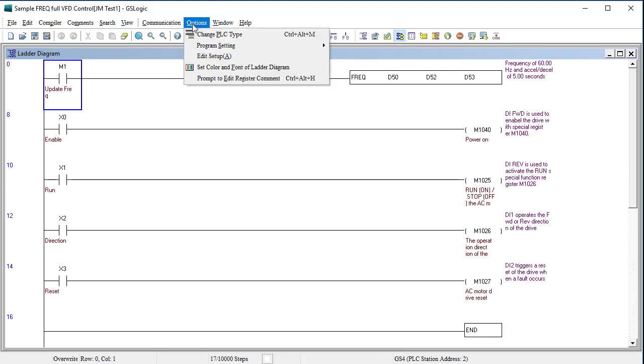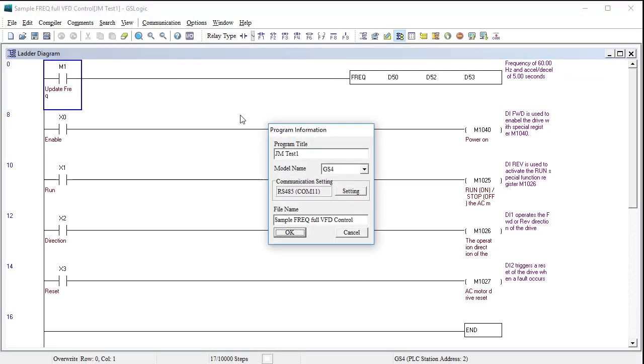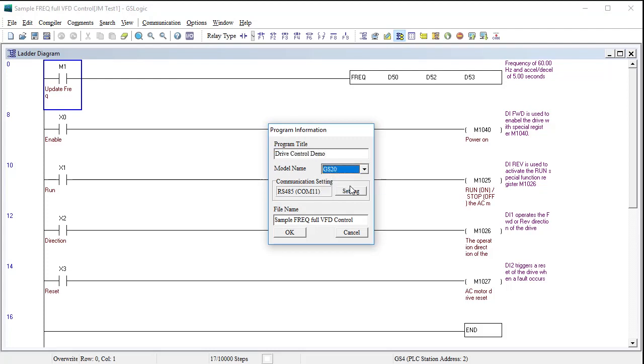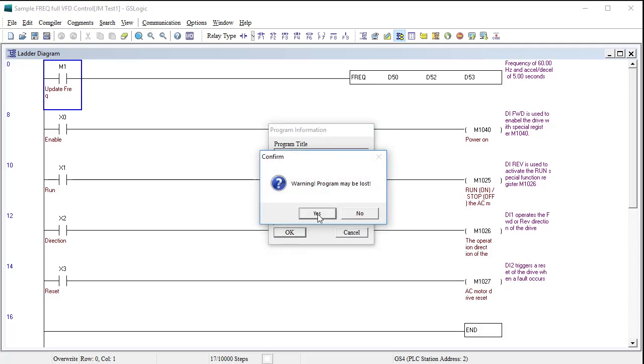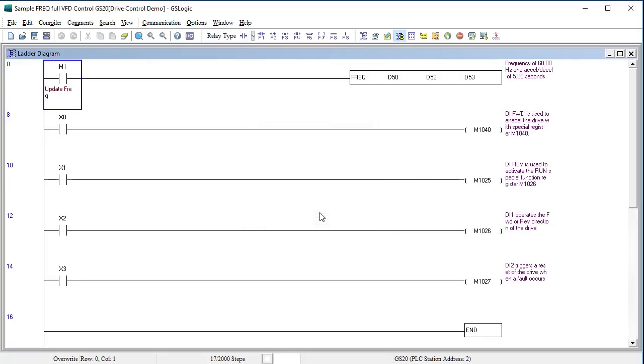The good news is, it's easy to change. We just go to options, change the PLC type, change the title, select a GS20 drive, verify we have the correct COM port and change the file name so we don't overwrite the original file. Now we have ladder code that is GS20 compatible and has the correct memory configuration.